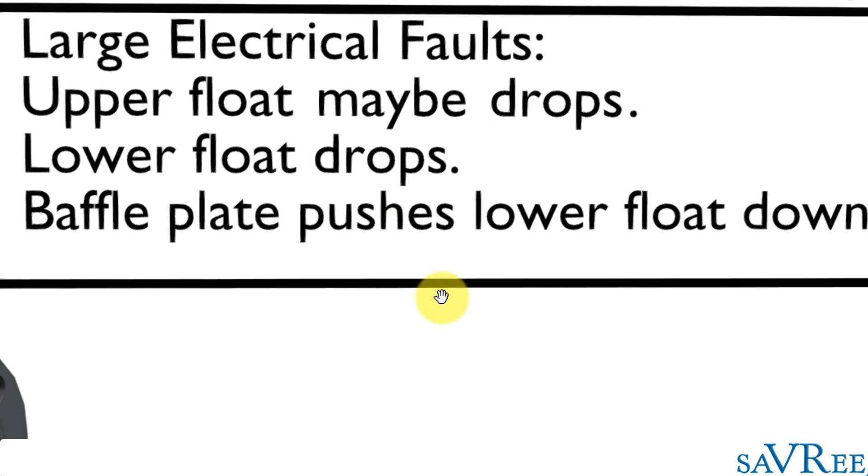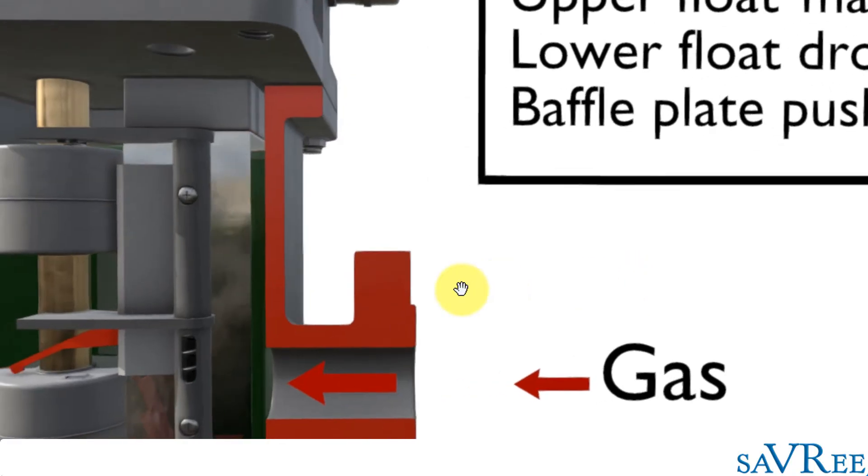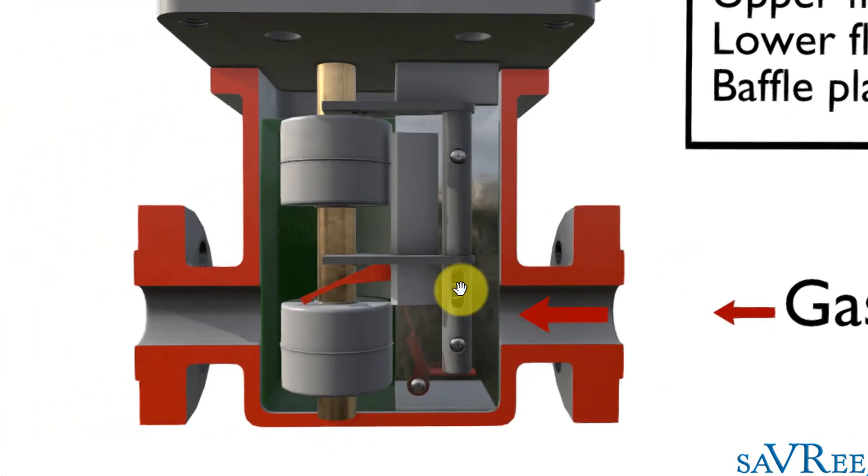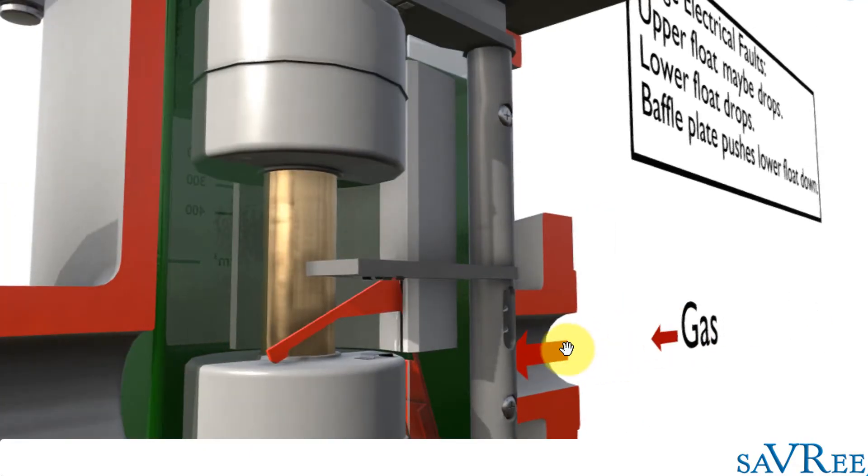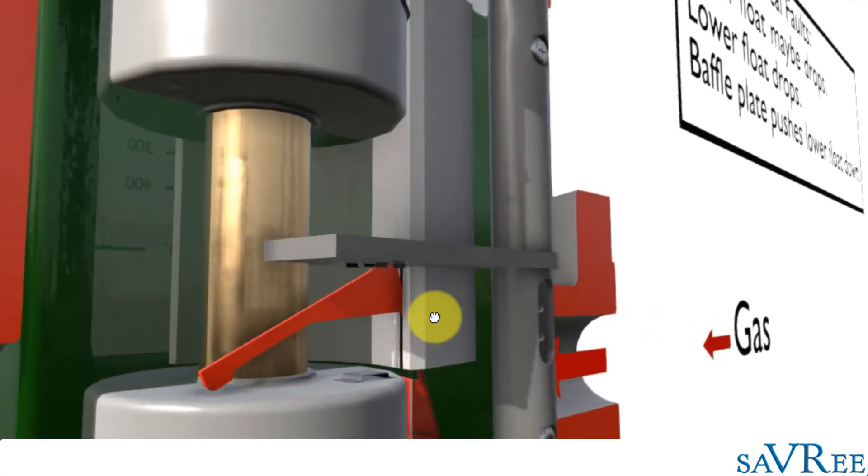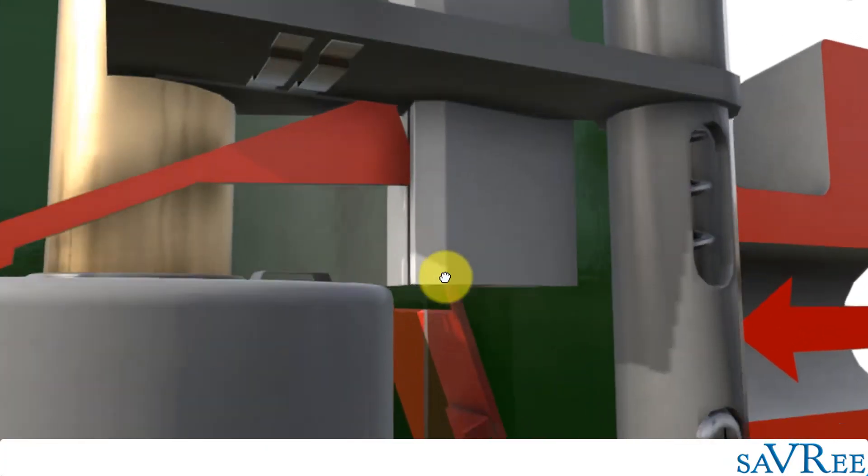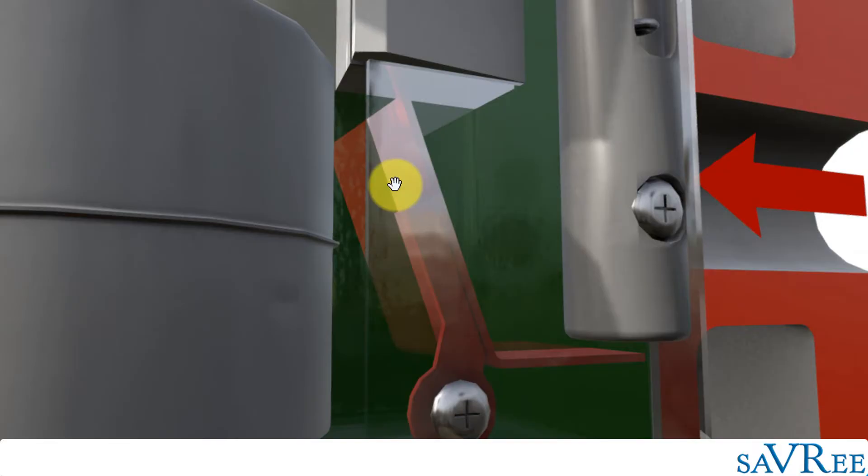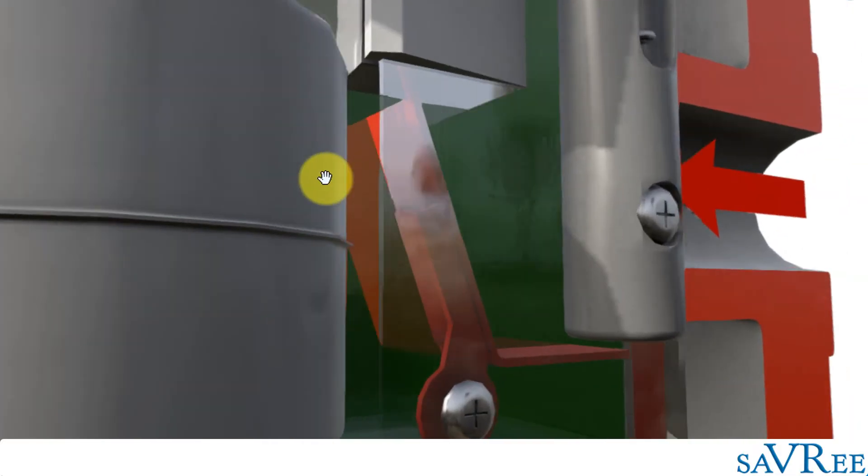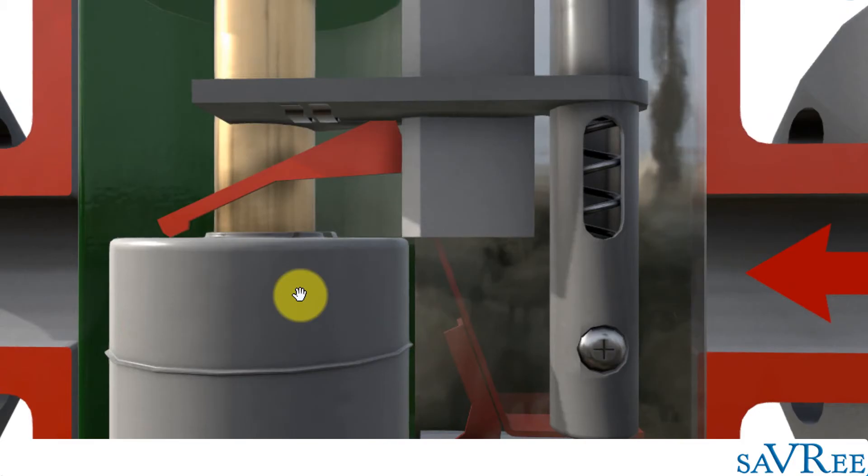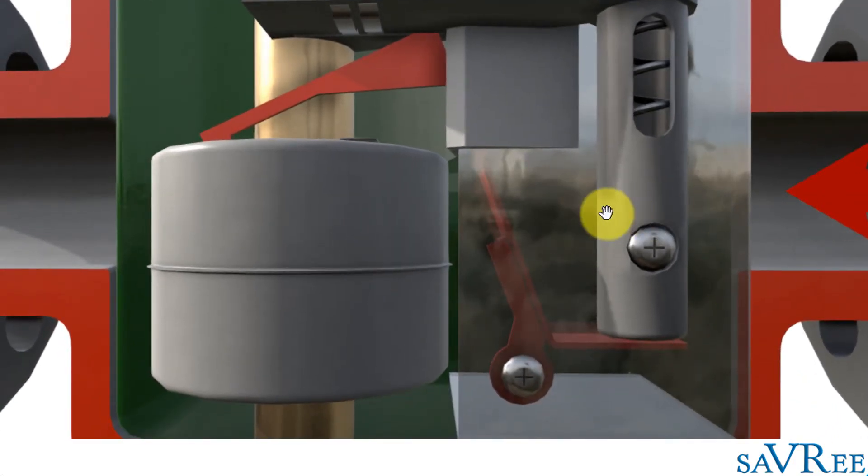Let's imagine we have large electrical faults. This large electrical fault has created a lot of gas in a very short amount of time. Because this gas is racing down the pipe, it's going to impact with this baffle plate here. It's going to push against that baffle plate and then force the lower float down. So massive inrush of gas pushes the baffle plate down, pushes the lower float down. And then that is going to shut down the transformer.